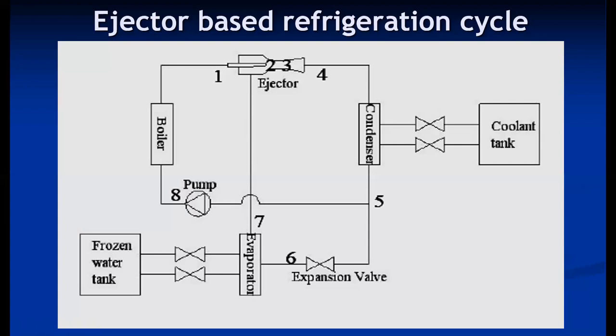The major difficulty of this system is its very low COP. From the numericals, we have seen that COP is less than 1, around 0.7. There are various configurations used to enhance the COP as well as to meet the application. Even so, COP is not a major concern because most of the energy required is low-grade energy to the boiler. If waste heat is available, as in a vapor absorption cycle, then the ejector refrigeration system is a good choice and COP becomes insignificant.